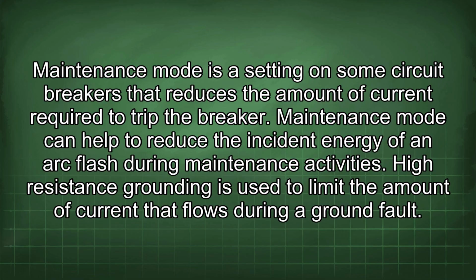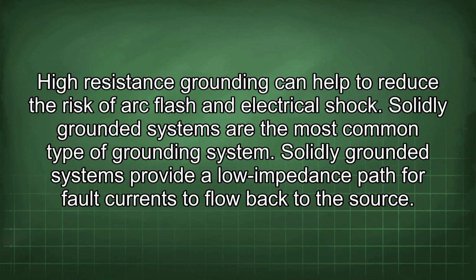High-resistance grounding is used to limit the amount of current that flows during a ground fault. High-resistance grounding can help to reduce the risk of arc flash and electrical shock. Solidly grounded systems are the most common type of grounding system. Solidly grounded systems provide a low impedance path for fault currents to flow back to the source.